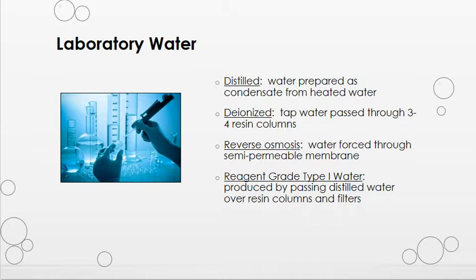In reverse osmosis, water is forced through a semi-permeable membrane, which removes most bacteria, particulate matter, and organic materials. However, small levels of contaminants may remain, so this type of water is not suitable for type 1 or type 2 water. Reagent grade type 1 water, which is the most pure, is produced by passing already distilled water over resin columns and then through filters. This type of water should be used to reconstitute controls and calibrators to prevent any contamination that could affect your lab results.